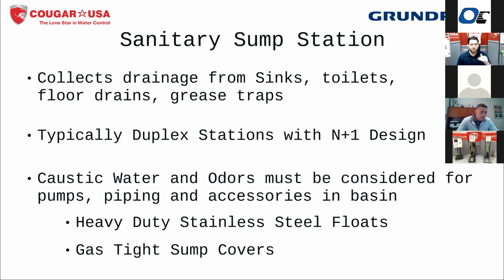So, when we're specifically talking about the grease, anywhere where there's a grease trap associated with it, because of the odors and the caustic nature of the water, we have some additional design considerations there. One being the heavy duty stainless steel floats. Our typical float switch is going to be plastic and a mechanical style float switch, good for most applications, even regular sanitary pits. But if it's a really nasty pit, you're going to want to move potentially to these heavy-duty stainless steel floats. We've got an example of those here.